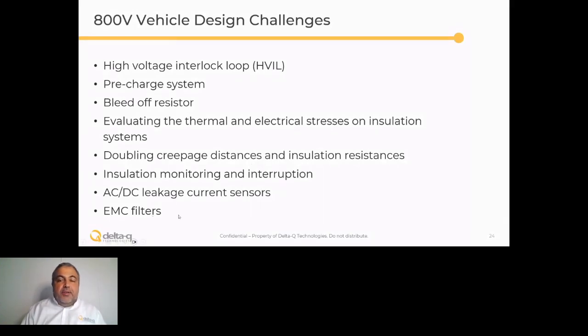Additionally, there are AC and DC leakage concerns. There need to be AC and DC leakage current sensors that are designed to monitor the resistance of conductor connections and continuously measure and analyze the residual and fault current, providing interruption if there are any faults.